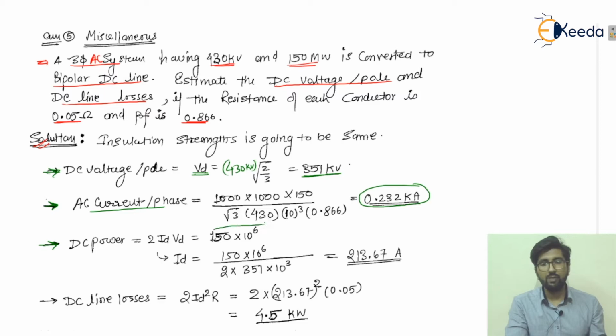This will be converted to DC power, which remains the same at 150 into 10 raised to power 6, that is 150 megawatt. Using the formula 2 into ID into VD, we find ID equals 150 into 10 raised to power 6 divided by 2 into 351 into 10 raised to power 3, where 351 is the VD voltage value. Calculating: 150 divided by 2 is 75, then divided by 351 and multiplied by 10 raised to power 3, giving us 213.67 amperes.